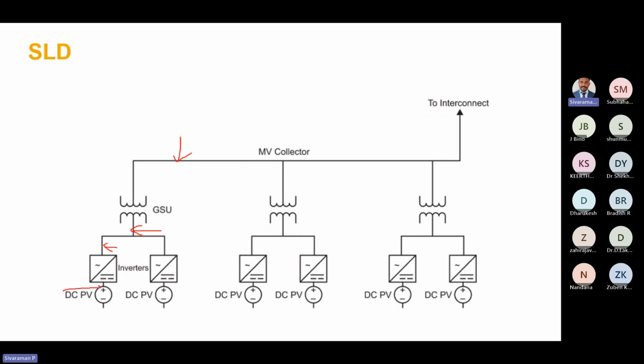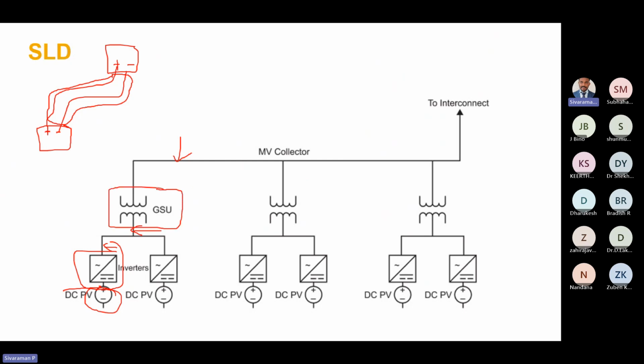Then the second one is the DC. This is an inverter, this is the PV panel. For example, this is the PV panel, with positive and negative, and this will be an inverter. We have to connect the positive and negative terminal of the panel to the inverter positive terminal. For this cable length we have to do the sizing and calculation. So we have to do AC cable sizing, DC cable sizing, and then inverter sizing also. These are some micro level steps.